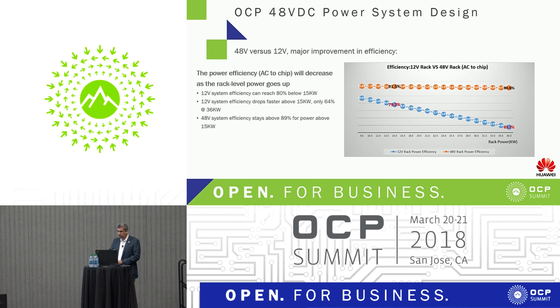It really starts to hurt above that 15 kilowatt number we mentioned, towards the left of the graph. 48 volt just continues—there's a slope down, but to show both on the graph, the 12 volt drops so dramatically, while 48 volt isn't dropping nearly as much in efficiency, even up to the 36 kilowatt load.